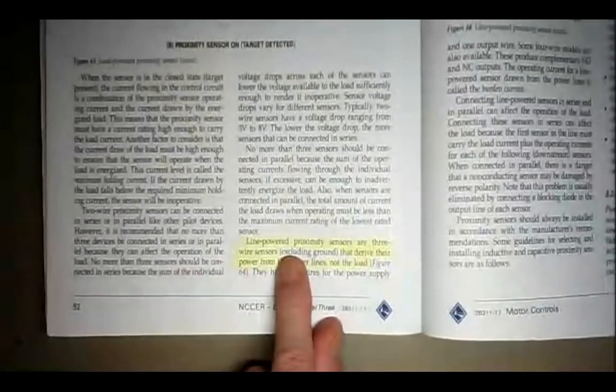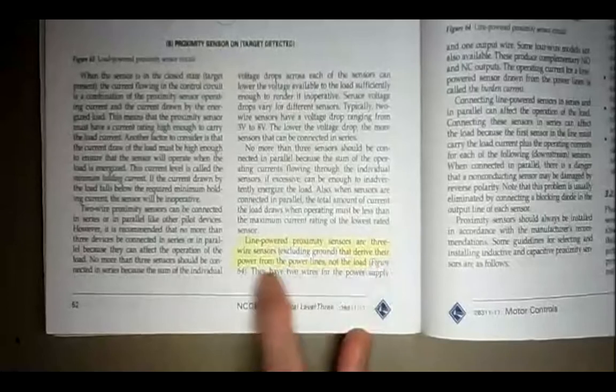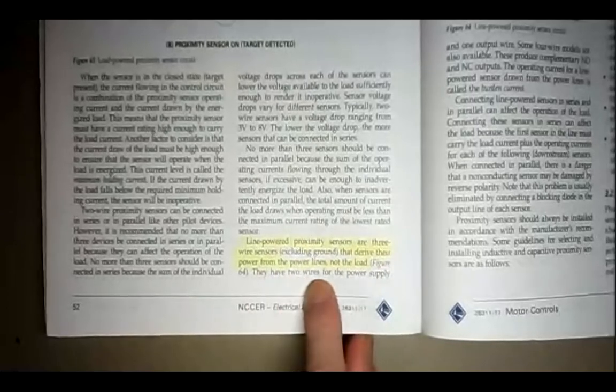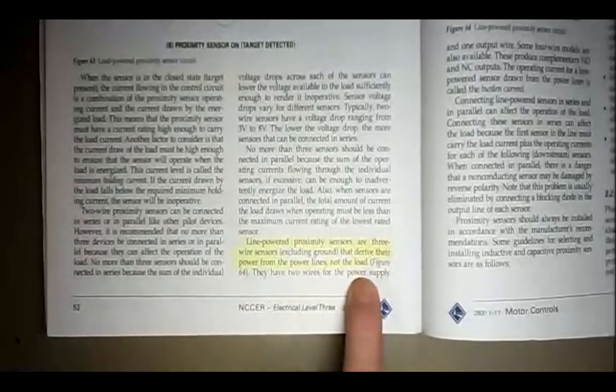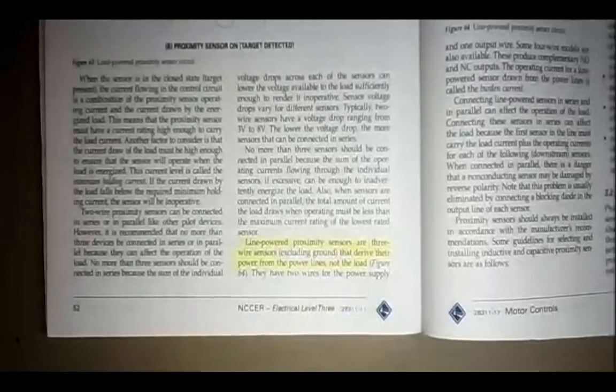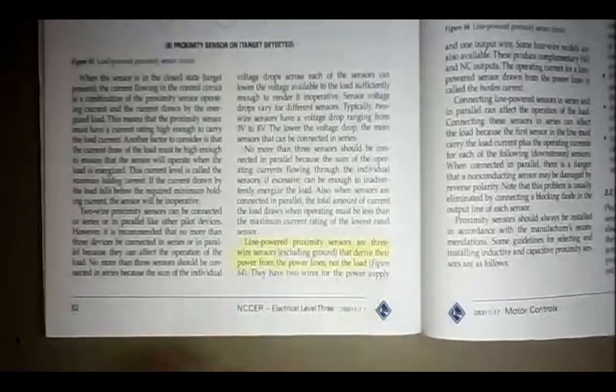And over here on page 52, it's talking about the line-powered proximity sensors. Line-powered proximity sensors are three-wire sensors, excluding the ground, that derive their power from the power lines, not the load. So they're line-powered. They're powered all the time, regardless of the state of the load. The load-powered is only working through the load.